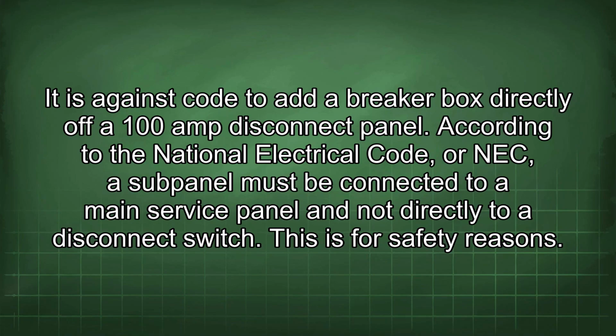It is against code to add a breaker box directly off a 100 amp disconnect panel. According to the National Electrical Code (NEC), a subpanel must be connected to a main service panel and not directly to a disconnect switch. This is for safety reasons.